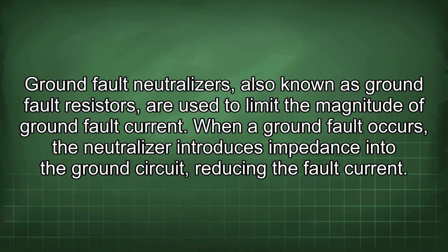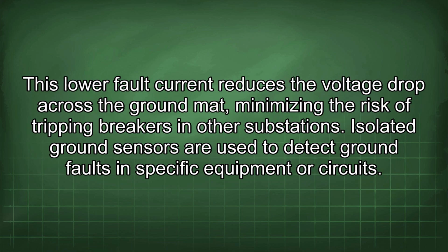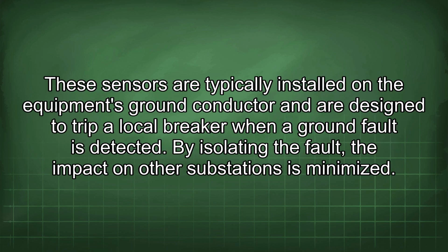Ground fault neutralizers, also known as ground fault resistors, are used to limit the magnitude of ground fault current. When a ground fault occurs, the neutralizer introduces impedance into the ground circuit, reducing the fault current. This lower fault current reduces the voltage drop across the ground mat, minimizing the risk of tripping breakers in other substations. Isolated ground sensors are used to detect ground faults in specific equipment or circuits. These sensors are typically installed in the equipment's ground conductor and are designed to trip a local breaker when a ground fault is detected. By isolating the fault, the impact on other substations is minimized.